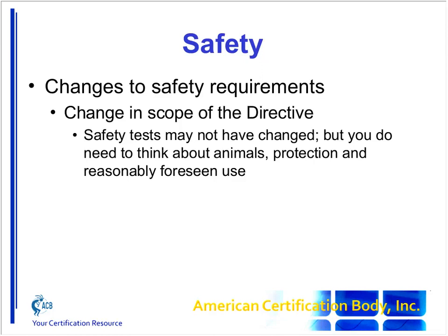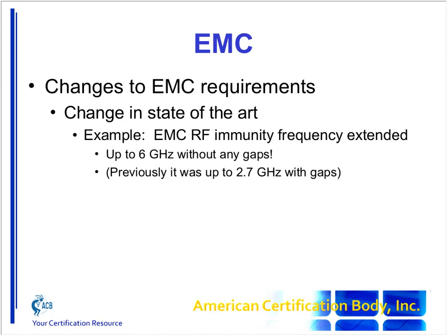For EMC, there's a change in the state of the art. It's not a change in the standards as such, but it's led to a change in the standards. For example, EMC RF radiated immunity. Previously, you would have tested from 80 megahertz up to 1 gigahertz, and then again from 1.4 to 2.7 gigahertz. Whereas now the test cases go all the way from 80 megahertz to 6 gigahertz without the big gap, and the exclusion bands are smaller.